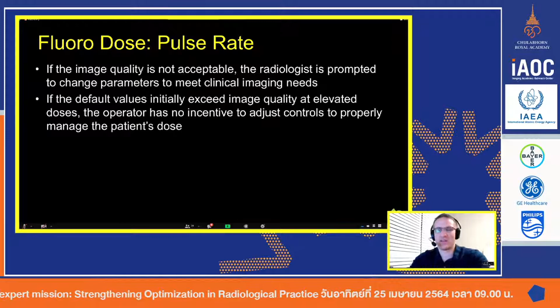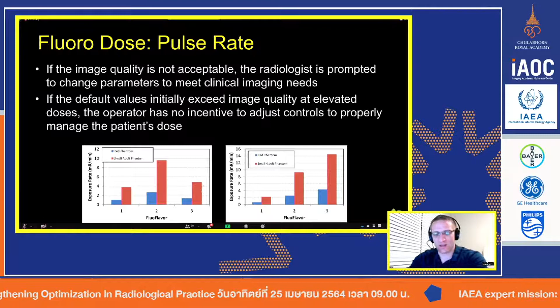Now, when you do this, I have 2 examples down here. This is a machine that I worked with, and you can see the 3 buttons on the machine would reasonably go from low, medium, high, which you see on the right graph. The irony is it actually went from low, high, medium. And every time I would go into service and work on this machine, I would adjust it, and then I'd go back the next year and it was all mixed up again.